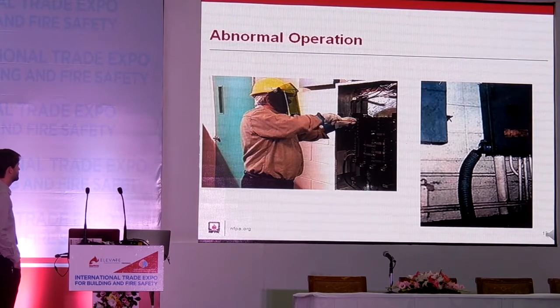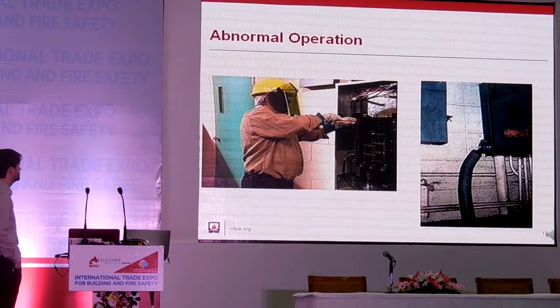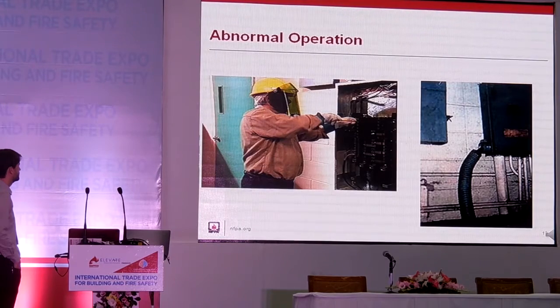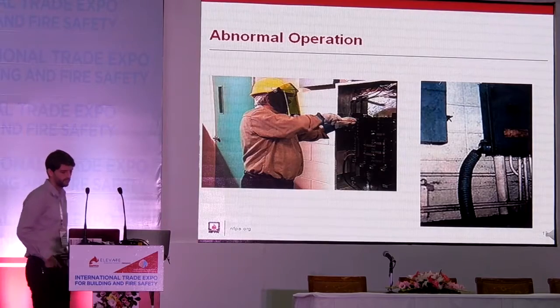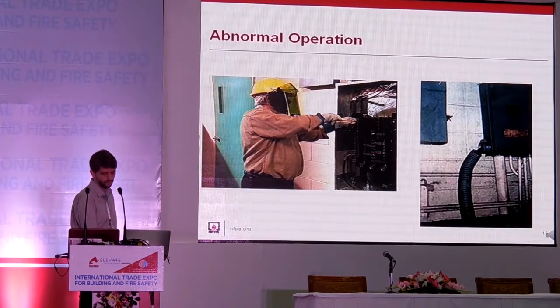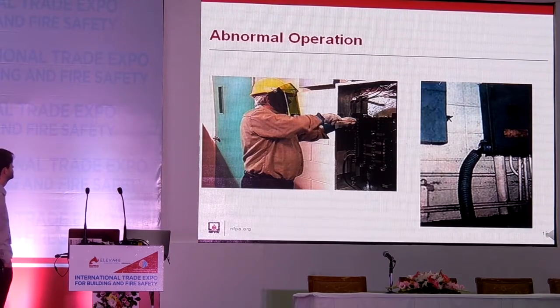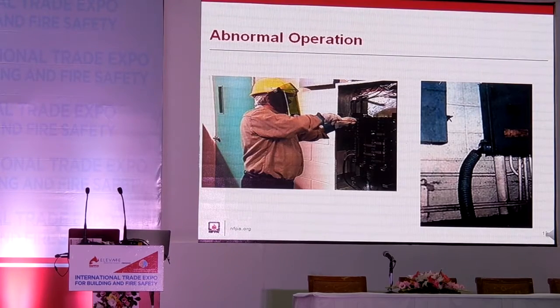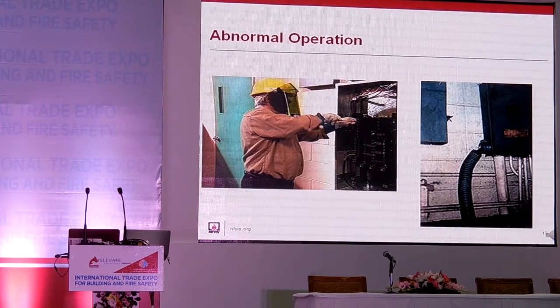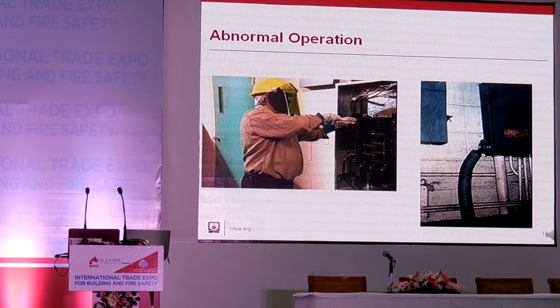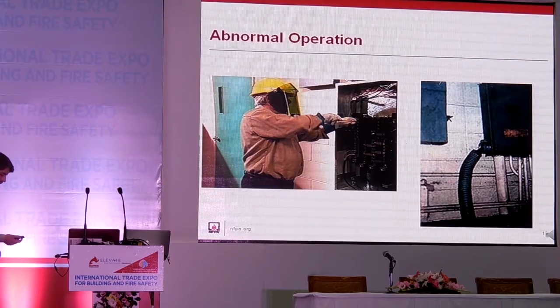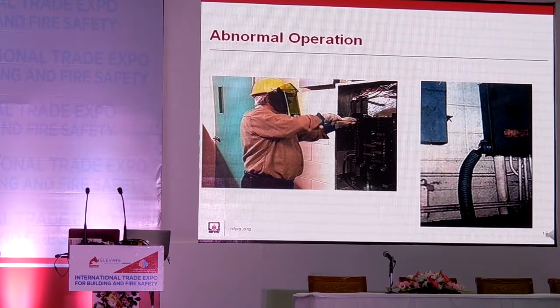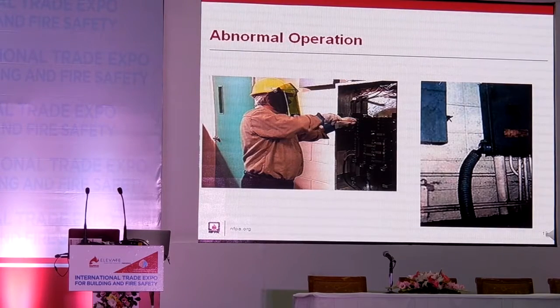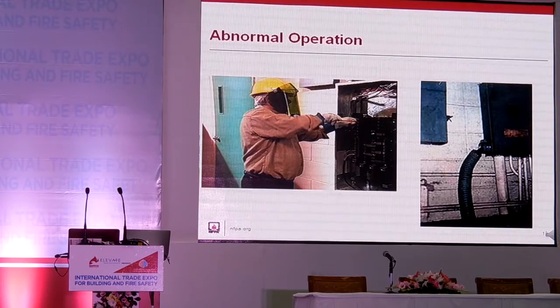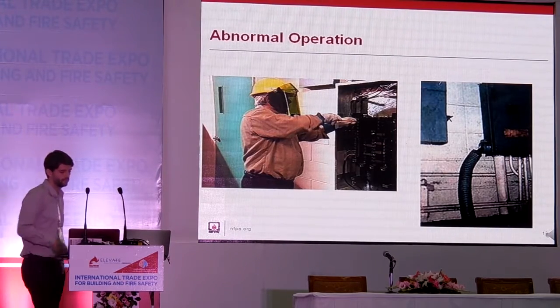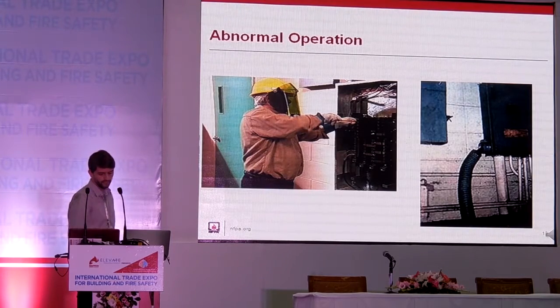As shown in the photograph on the left, the worker is working within an energized panel board. And because the safeguard of the cover is no longer in place, the worker is using personal protective equipment commensurate with the task and the hazard associated with that particular task. In the photograph on the right, improper maintenance of the equipment is evidenced by the fact that the flexible conduit has pulled out of the fitting. There is no assurance that the conductors within the flexible conduit have not been abraded, and there is a potential shock hazard. These are both examples of abnormal equipment operation.